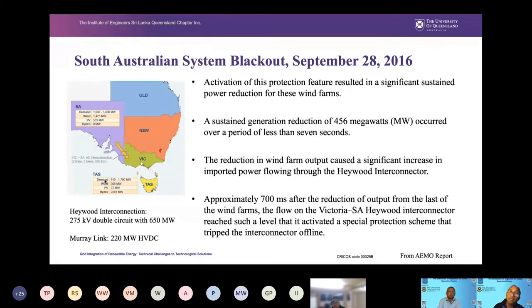So with the reduction in wind farm output, the system has to rely on somewhere else. So they go for the interconnections and try to get more power from those interconnections. As a result, maximum power was trying to flow from the Heywood interconnection. So that also went to the maximum capacity, the Heywood capacity. At that time, the Murray Link, the second interconnection, was already operating at the maximum capacity.